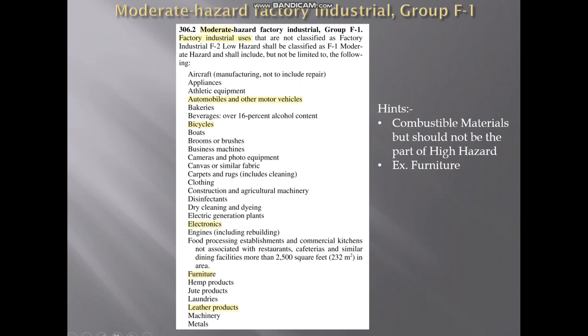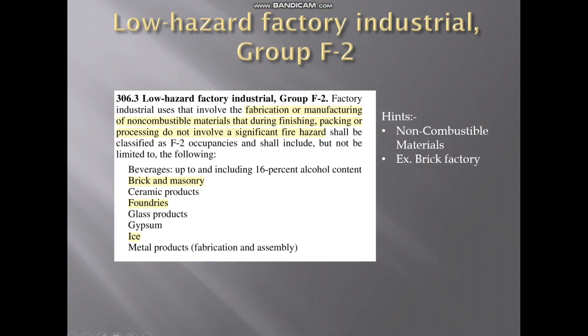In moderate hazard F1, you can see combustible materials like furniture, leather products, and bicycles — these come under moderate hazard, not high hazard. In the next category, F2 is low hazard, dealing with non-combustible materials — fabrication or manufacturing of non-combustible materials. For example, a brick factory, which will not produce any highly flammable or high hazard items. Similarly, foundries come under this low hazard subgroup.